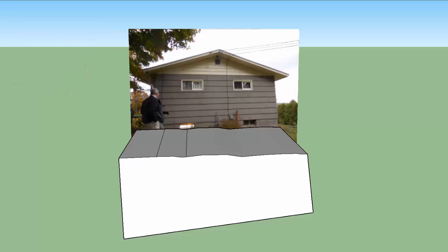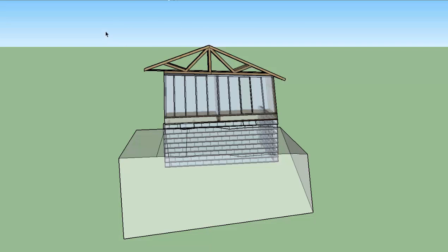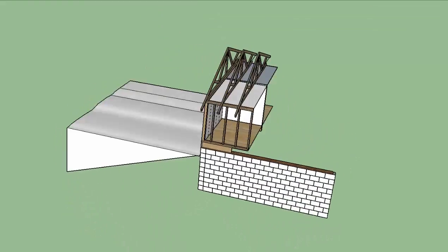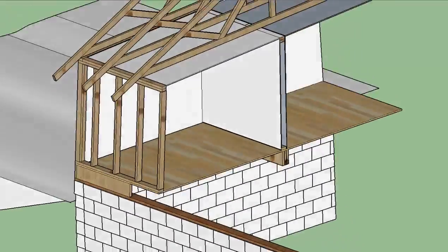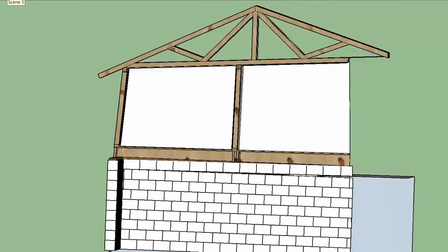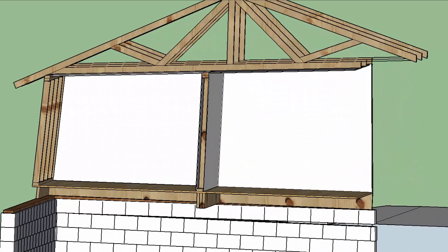This short video will describe how the stack effect works in a house, creating heat loss and cold air infiltration during the heating season. Here we have a classic ranch-style house, one floor of living space with a full-height basement. To show how the stack effect works, we will be removing the exterior walls and some of the sheetrock to let you see into the structure of the house. Now we can see inside of the house.